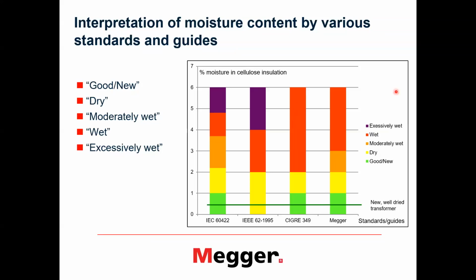There are different ways that you can go on a dry-out process in the field, right? It depends on the ability and the equipment and many different things, even the environmental conditions you have on site. What is most effective for a dry-out, considering that the unit is wet? Because if you just process the oil, that will take a long time to dry the solid insulation. So what you do is what we call the high vacuum and thermal process. You apply vacuum and temperature to extract the moisture from the transformer.